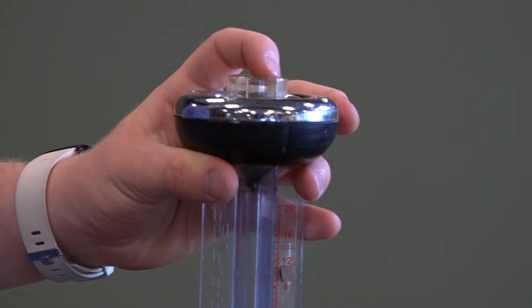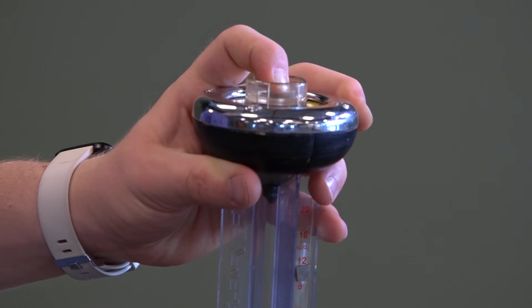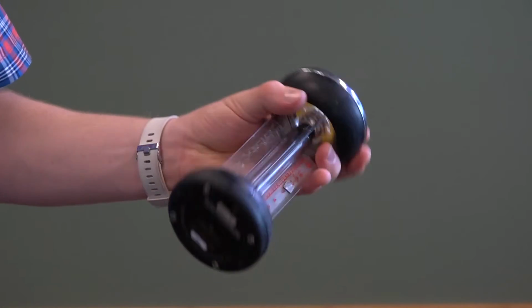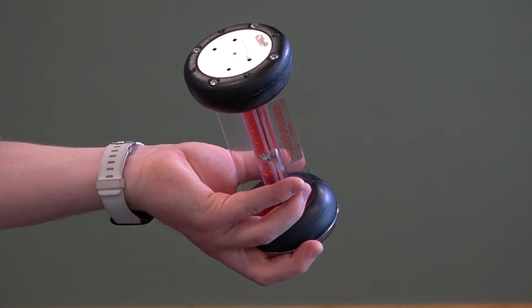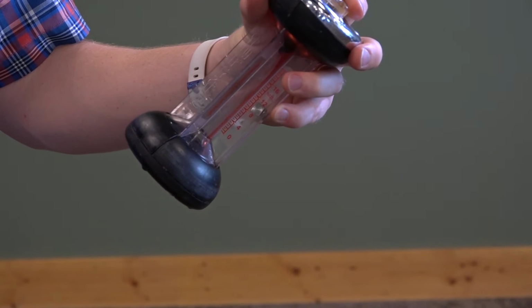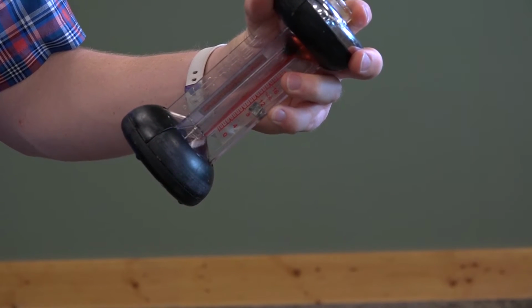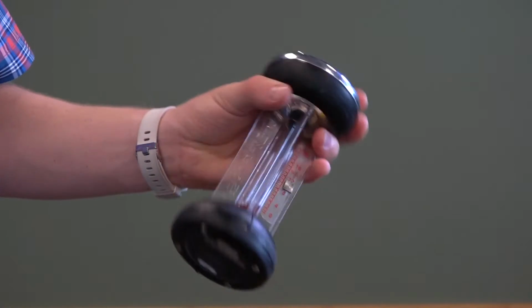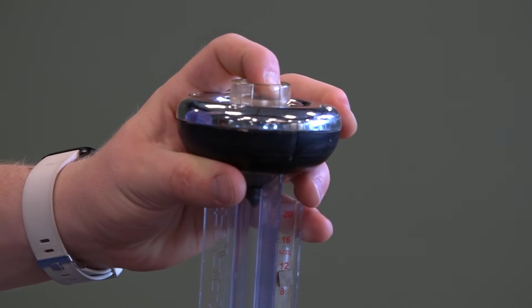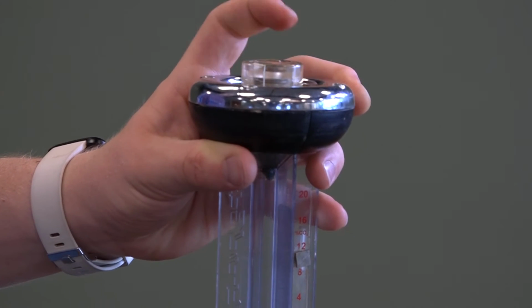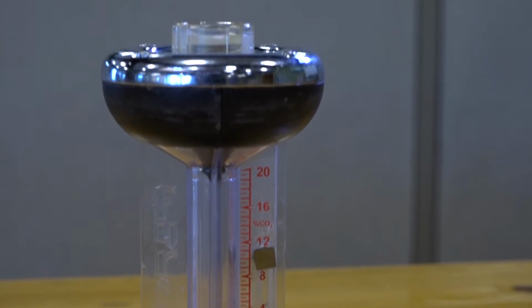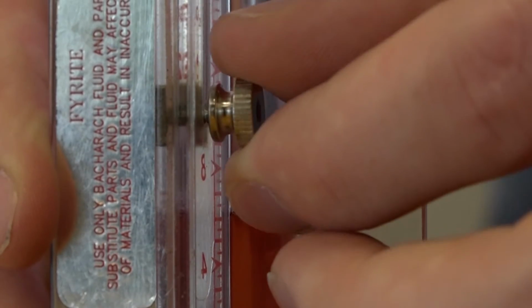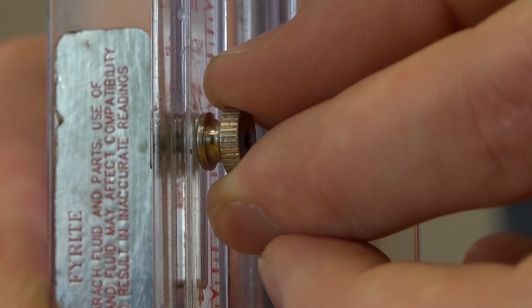To calibrate the meter, mix the air and the solution by doing this process twice. First, push in the meter's valve with your finger to vent it with air, then release it. Turn the meter almost completely over to fill its top reservoir, then turn it back upright, letting the fluid drain back down by holding it at a 45-degree angle. If the fluid doesn't drain to the level it was at earlier, flip it over again. Vent the fluid again, then repeat the process a second time. Next, while holding the meter upright, loosen the lock nut and slide the scale until the 0 line is level with the top of the liquid.